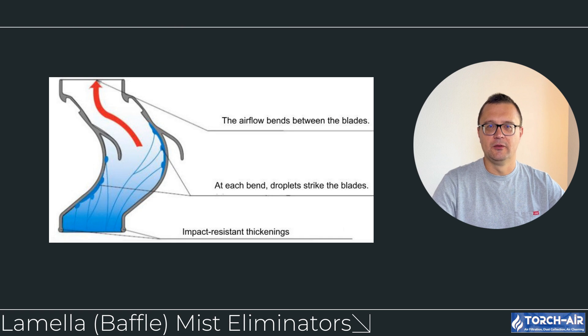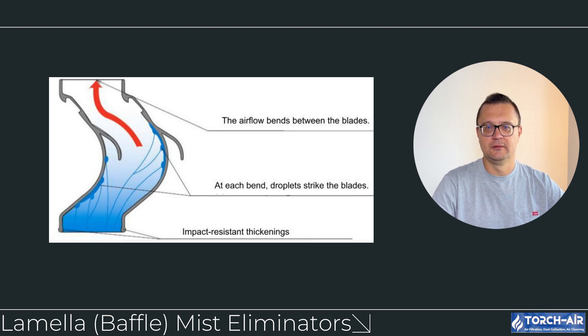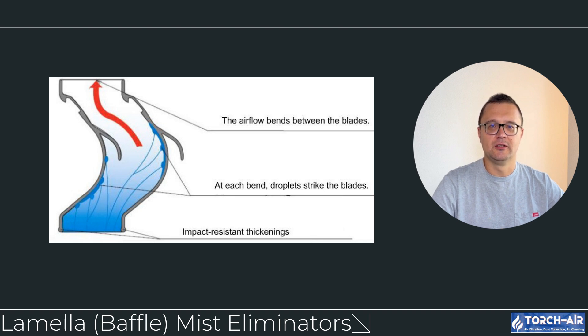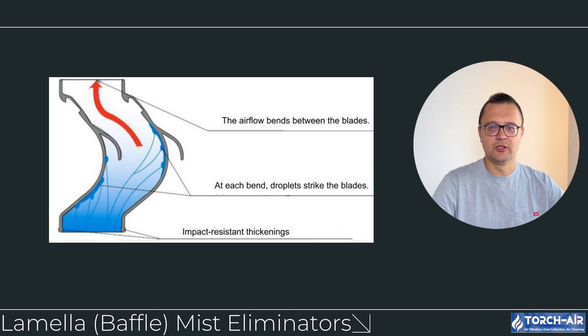Lamella, or baffle, mist eliminators consist of thin, flat or corrugated plates arranged in parallel. As the gas stream moves through these plates, the droplets are captured and drained by gravity. Best for medium to fine droplet sizes, they offer high separation efficiency for a range of droplet sizes with minimal maintenance required. The plates must be spaced properly to avoid airflow blockages or reduced efficiency.